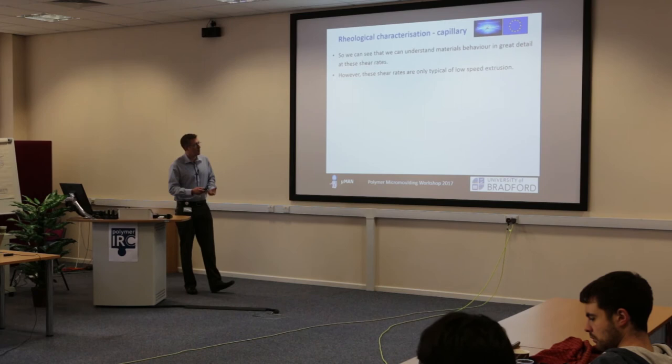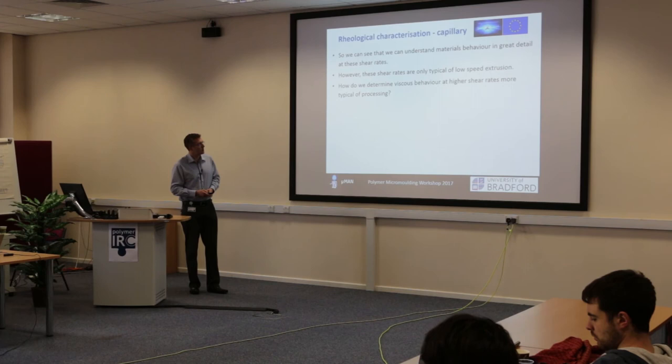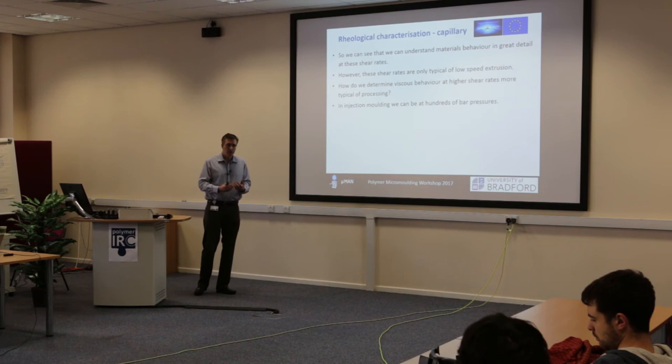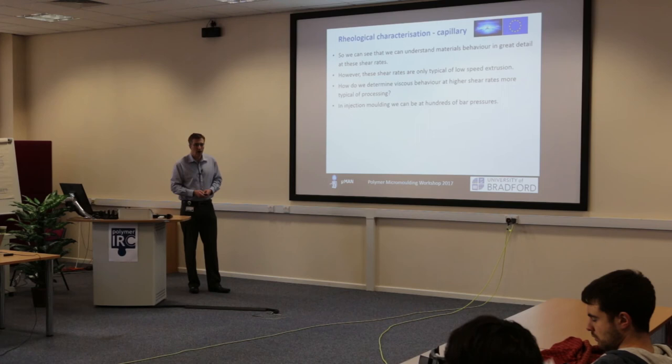So in the rotational rheometer, we can get up to processing rates that are similar to what we would see in a fairly slow extrusion process, but not so much a higher rate process like injection molding. Also, the real processes are at very high pressures. Because they're pressure driven, to generate high flows, we have to use a very high pressure. So our pressure can be hundreds of bar in these systems.